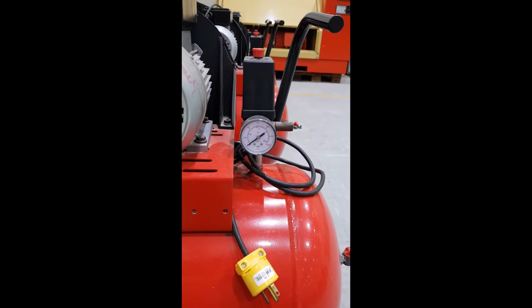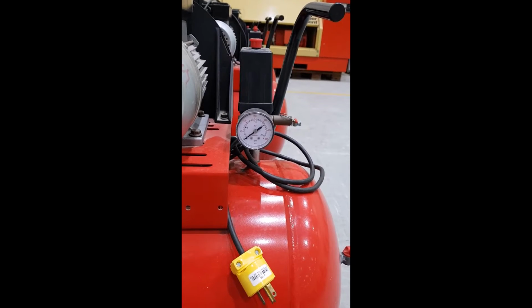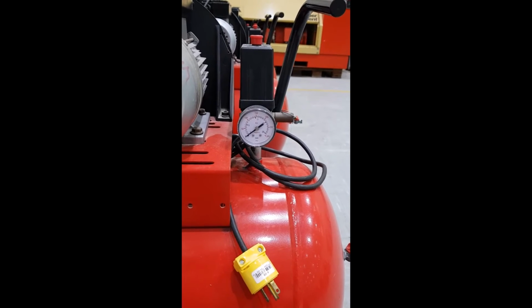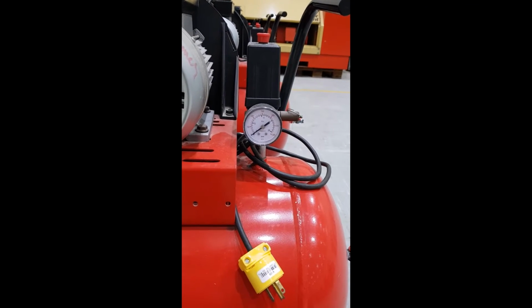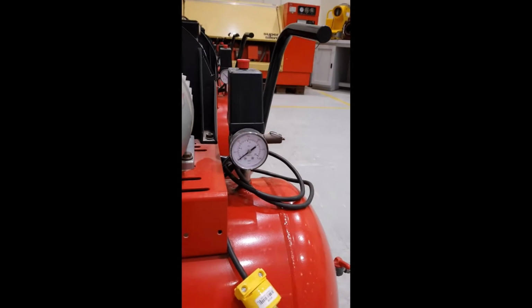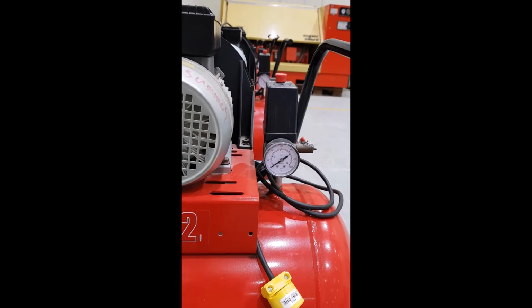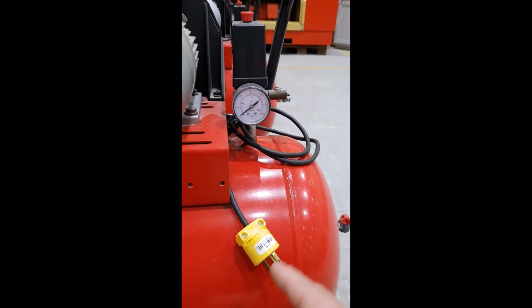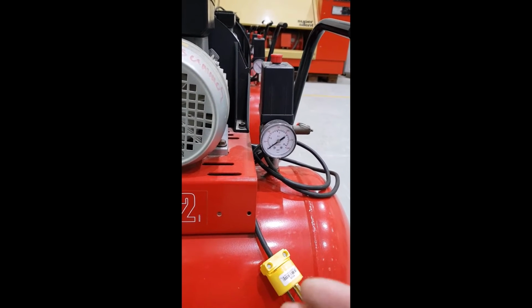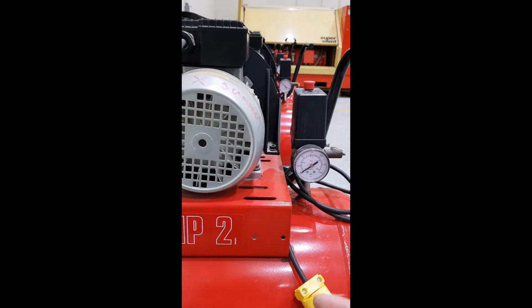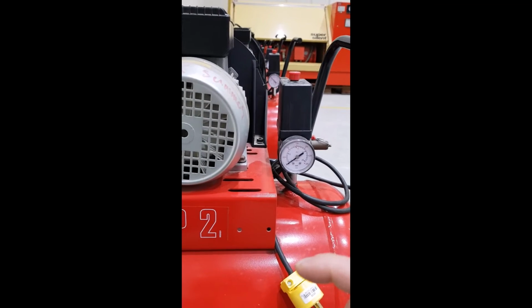Now, for a long time period between the charge and discharge, or stop and start again, if the period is too long, then we use the regular compressor. If the time period is medium, we are talking about an hour, 2 hours, maybe we can use the on and off cycle compressor.